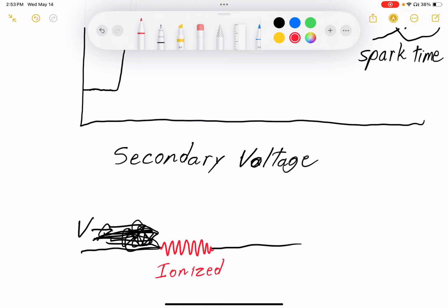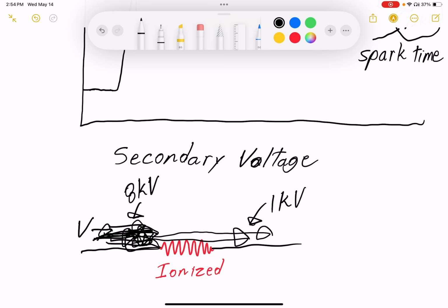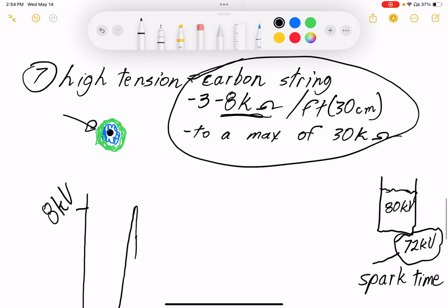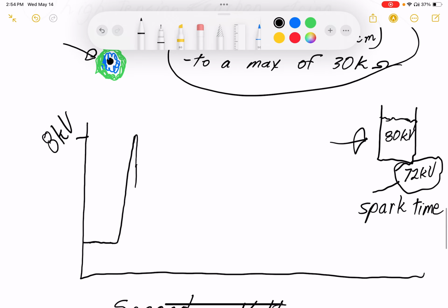it will require considerably less energy to maintain that ionization, because now it's got a path, right? Now the bridge has been built. So it may have required, you know, 8,000 volts to push across the gap, but it may only require 1,000 volts to maintain current across the gap. But that's voltage over time, right? Because those volts are still flowing, and that coil only created so much, that bucket only has so much voltage available in it. As it's consuming 1,000 volts at a consistent rate to keep that gap ionized, it's going to deplete that bucket of available voltage in the coil quite quickly.